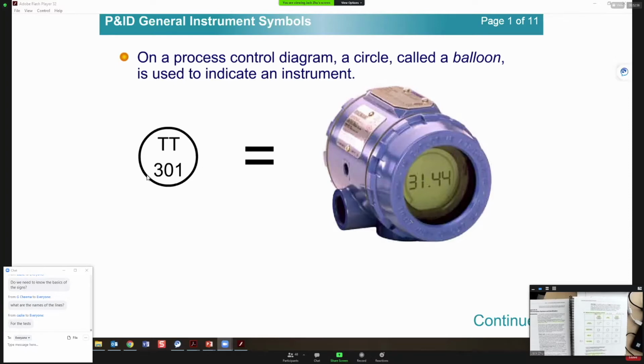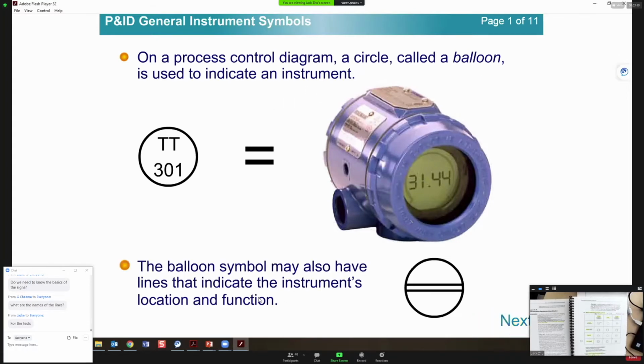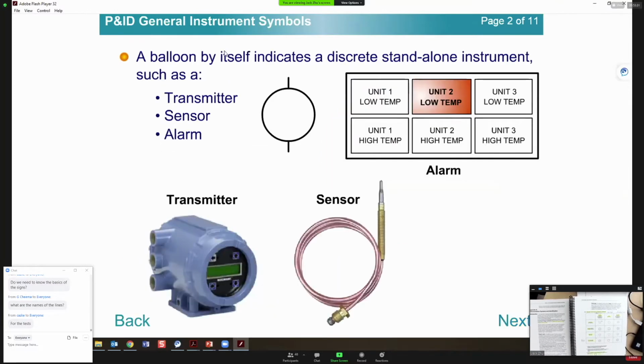or P&ID diagram, you will have those symbols on there. They usually have letters, they usually have numbers, and they call them balloons. They usually indicate an instrument. Some of the balloons will have lines inside. The line is trying to indicate the instrument location and the functions. So you will have that in your book. It also tells you certain things down there. If you just have a balloon by itself, it's a discrete instrument. If you have a transmitter, sensor, or alarm, that would basically be a simple circle or balloon.